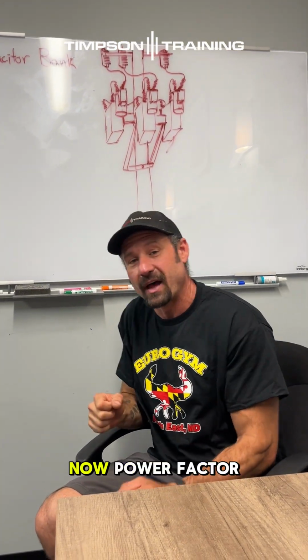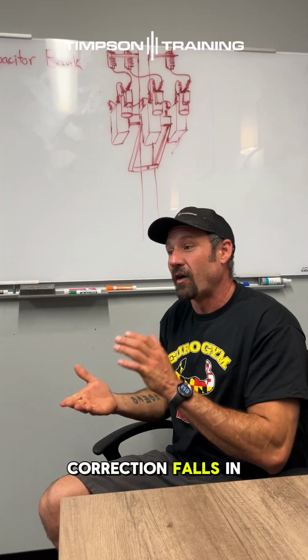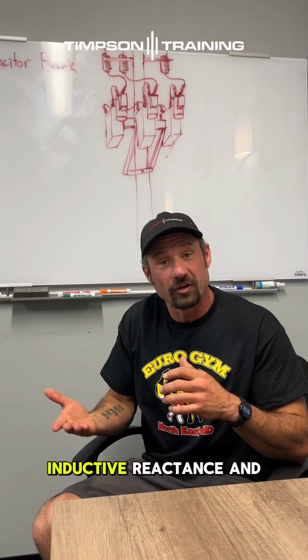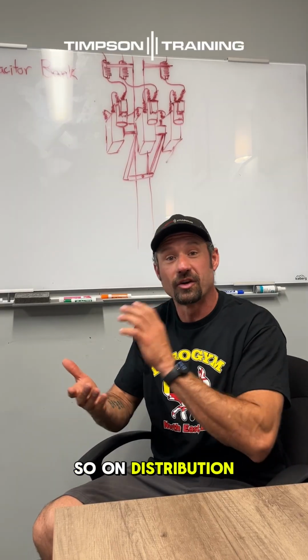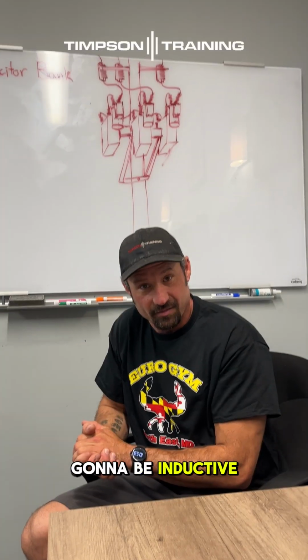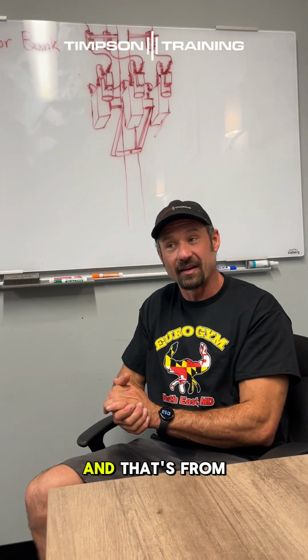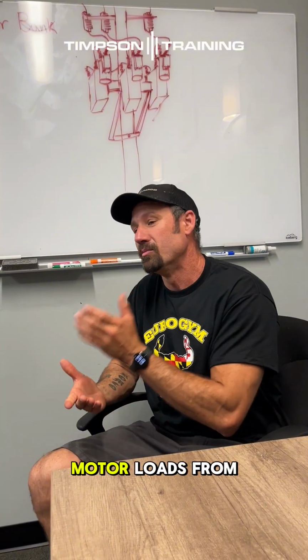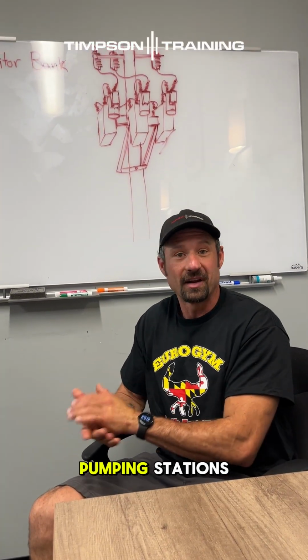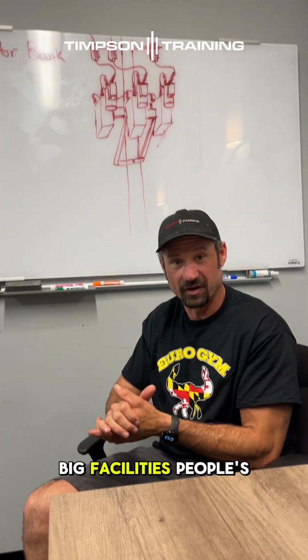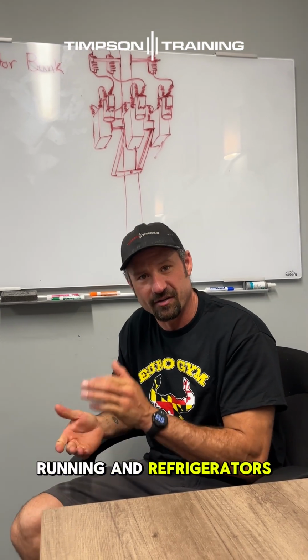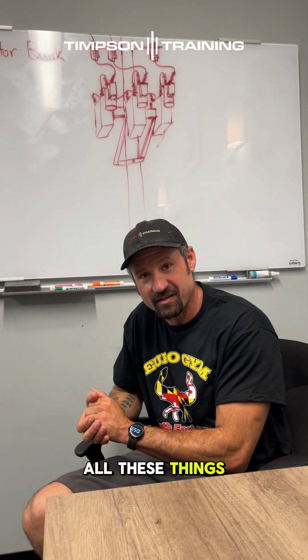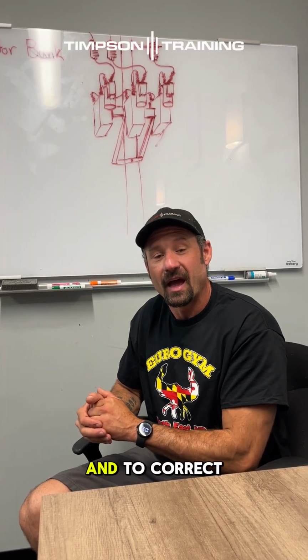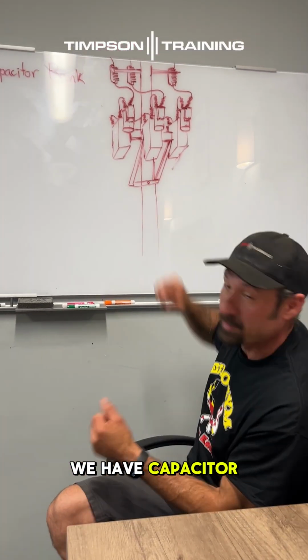corrects power factor. Now, power factor correction falls in with inductive reactance and capacitive reactance. So on distribution lines, for distribution linemen, we're almost always going to be inductive. We're going to have inductive reactance on the line, and that's from a lot of transformers, motor loads from factories, pumping stations, big facilities, people's homes. You have a lot of houses with ACs running and refrigerators and well pumps. All these things make inductive reactance. And to correct that, we have capacitor banks.